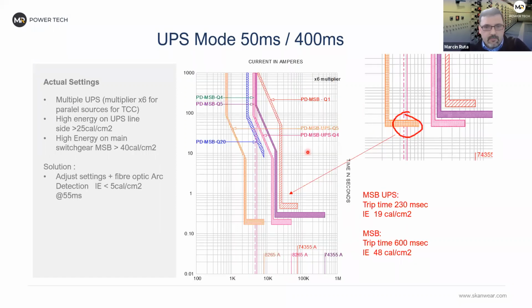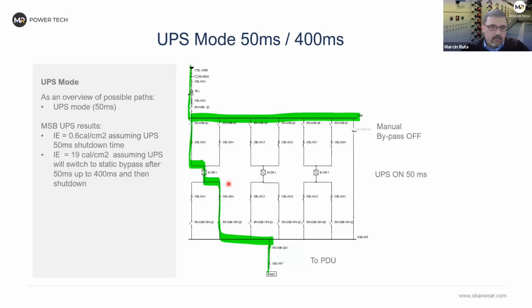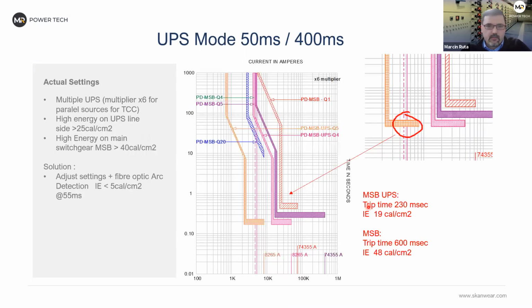So just to explain a bit why. If you maybe saw here, we have parallel breakers for each UPS. It's not my design, that's what I got. And if you will see, the breaker is faster than UPS, it trips in 230 milliseconds, that's okay, but we'll end up with 19 calories.